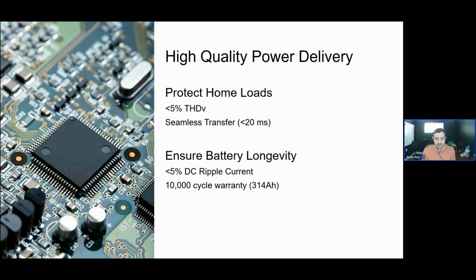That ripple current can heat the battery unnecessarily and cause microcycling of the battery, both of which are going to shorten the battery life. Or in a less extreme case, it can just confuse the battery and lead to inaccurate SOC calculations and readings, which will arbitrarily degrade the capacity of the battery, right? If your battery thinks it only has 85% SOC when it really is at 100, you're going to leave 15% on the table in the event of a discharge cycle of that battery. So really important to ensure that your power electronics or your inverter has low levels of DC ripple current, and the EG4 FlexBOSS unit certainly delivers on that with less than 5% DC ripple current.